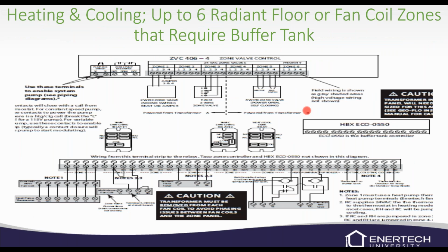This is a heating and cooling, up to 6 radiant floor or fan coil zones, where you're going to require a buffer tank. So you've probably got some smaller zones. In this application, we're going to use the HBX ECO 0550, which is going to be your buffer tank controller. And then there will be a couple of relays. Again, zone valves on the top here, and then your thermostats down on the lower portion of the plug and play terminal strip. Make sure that if you've got fan coils, that if they have transformers in them, that we remove them so we don't have phasing issues with the zone panel itself.